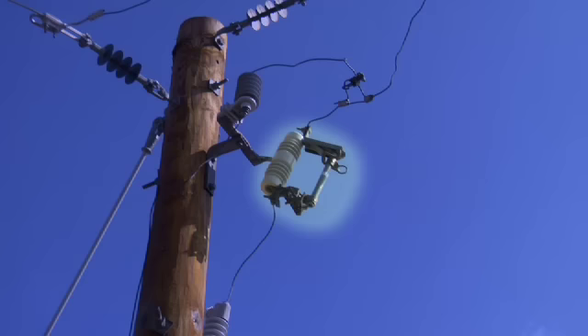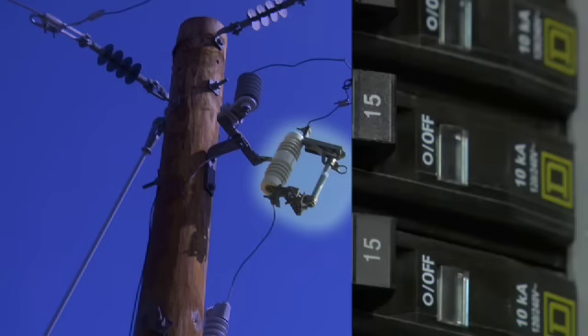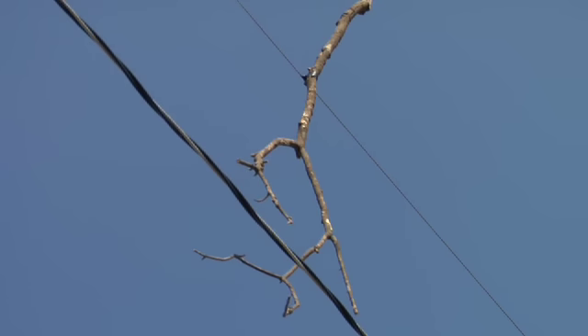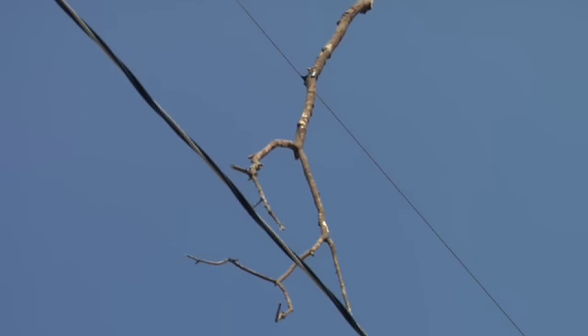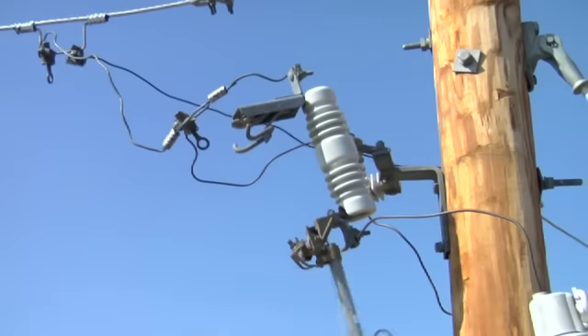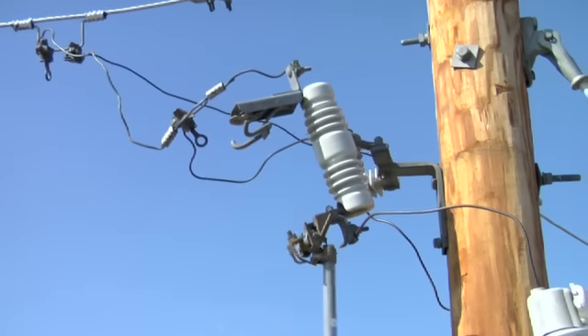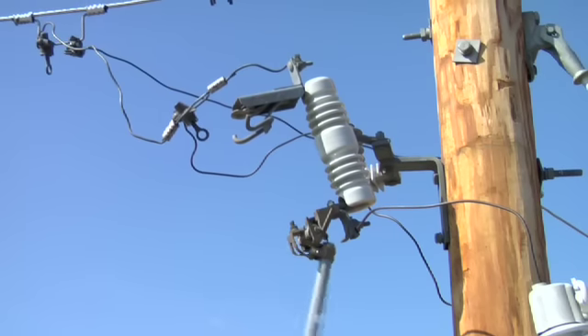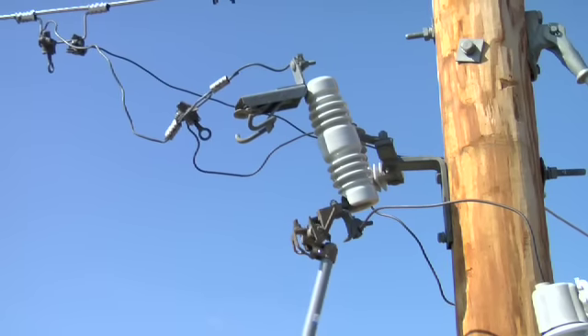At about the same level as the lightning arrestor is the cutout. A cutout is similar to a fuse in your home. It protects the pole and its equipment from too much electricity. If a squirrel or tree branch were to come in contact with a wire, the cutout will open, indicating a problem with that section of the line. If you ever see an open cutout, be sure to call your power company.